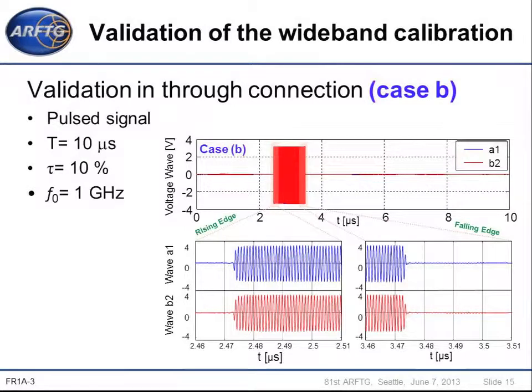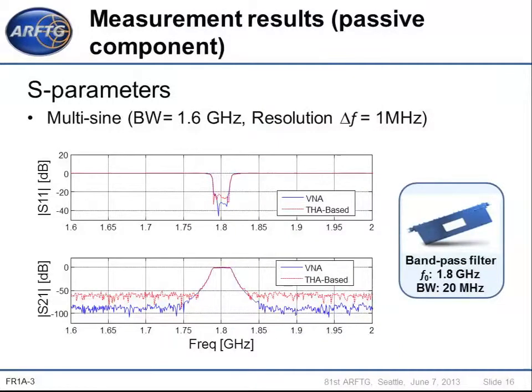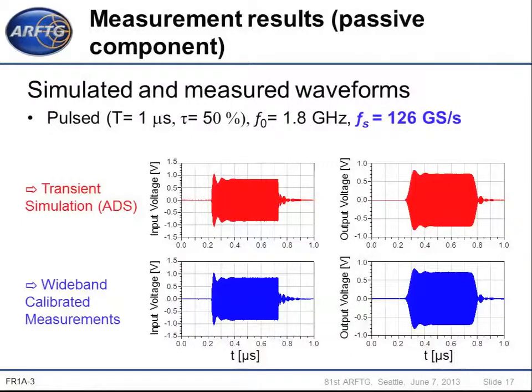Now in case B, the measurement system is calibrated using the proposed wideband calibration. We can show very good coherence between incident and transmitted voltage waves, and the rising and falling edges are clearly observed without any distortion. Thus we validate this calibration procedure. To show the accuracy of the measurement system in S-parameter measurement of a passive component, we made the S-parameter measurement of a bandpass filter using the multi-sine signal in a bandwidth of 1.6 GHz and a resolution of 1 MHz. We compare S-parameter measurements between VNA and the proposed THA-based system, and we observe very good coherence between them. We also perform time domain characterization under pulsed excitation for the passive component.